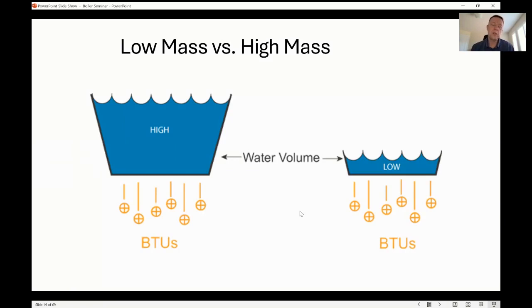So if you take a look here, this kind of shows the difference between low mass and high mass. If you have the same amount of BTUs on the bottom, you can take a look at the right, that low mass heat exchanger there. You can see if you slow down that flow too much, there's not a lot of water there to absorb the BTUs. And if that's too slow, what will happen is you'll flash the steam really quickly. And a water boiler that's not designed to be a steam boiler generally doesn't like that. It can cause all kinds of issues with your system and your boiler.